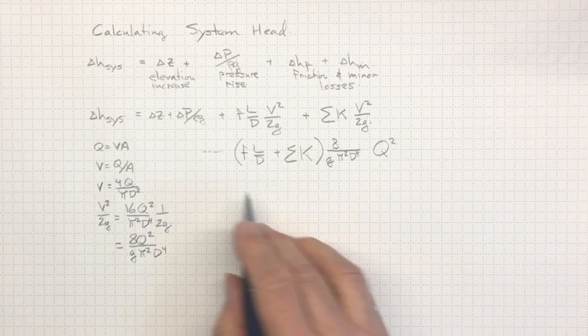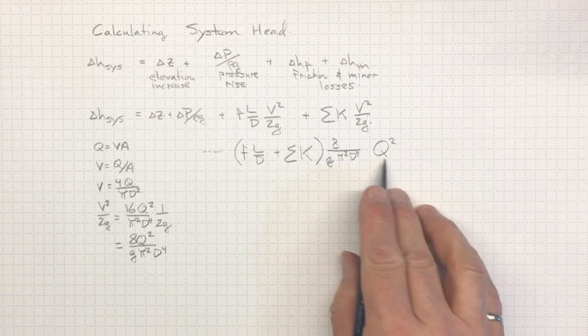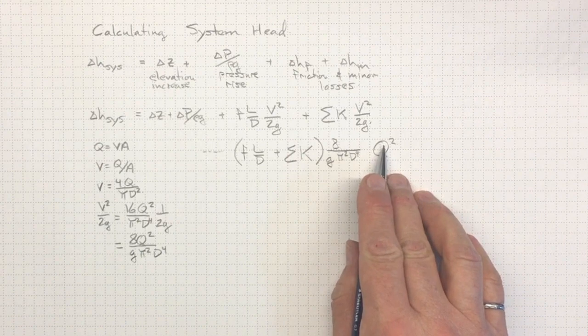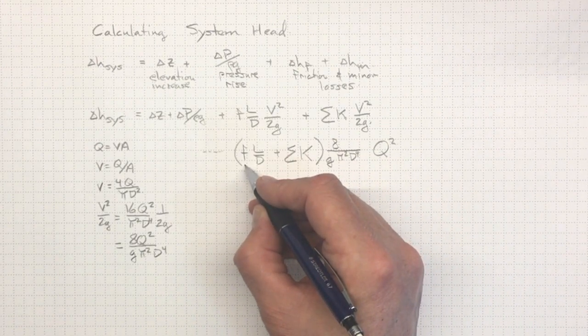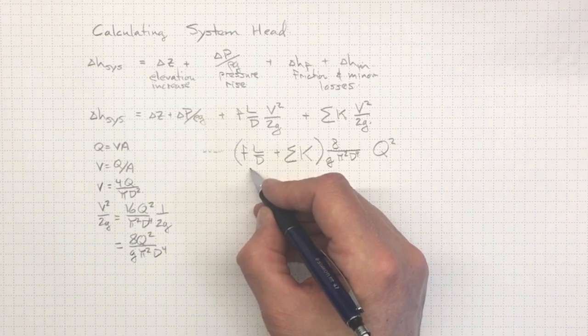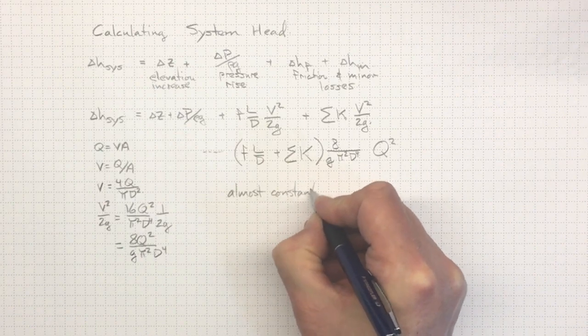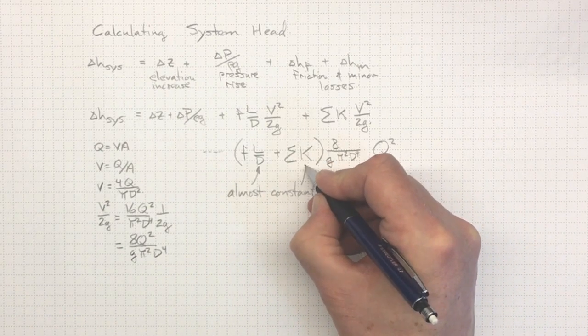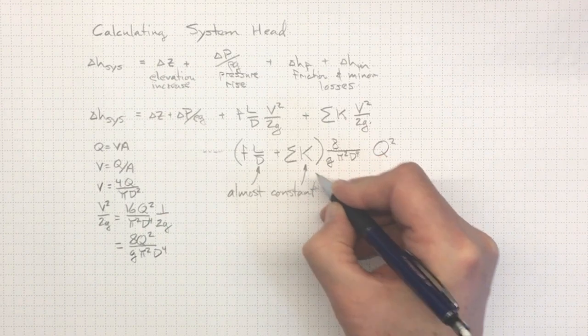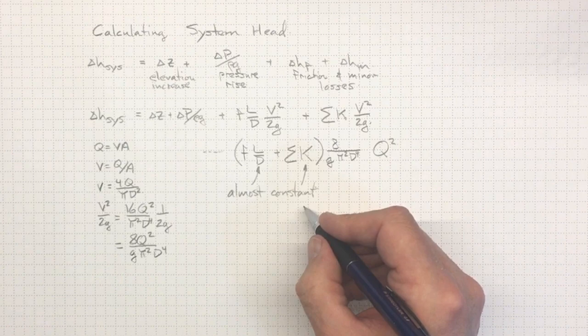Now let's think about how we might go about calculating this portion for varying flow rates. Now, friction factor, it's a weak function of the flow rate. It's a function of Reynolds number and relative roughness, but it's almost constant.